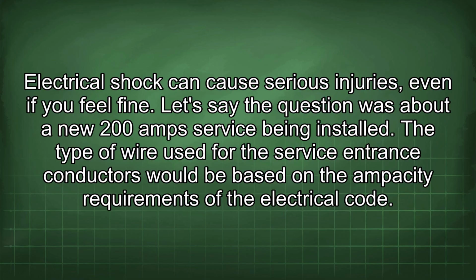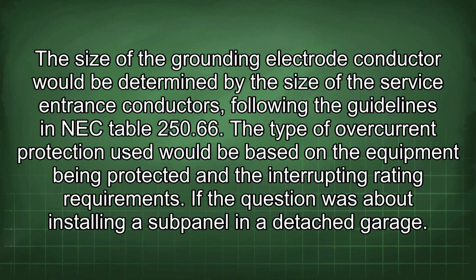Let's say the question was about a new 200 amp service being installed. The type of wire used for the service entrance conductors would be based on the ampacity requirements of the electrical code. The size of the grounding electrode conductor would be determined by the size of the service entrance conductors following the guidelines in NEC Table 250.66. The type of overcurrent protection used would be based on the equipment being protected and the interrupting rating requirement.